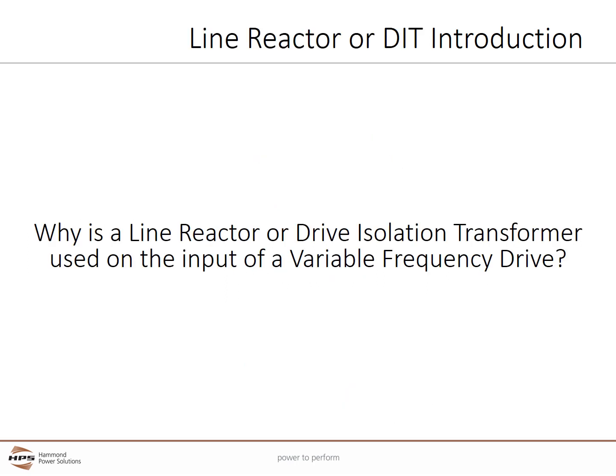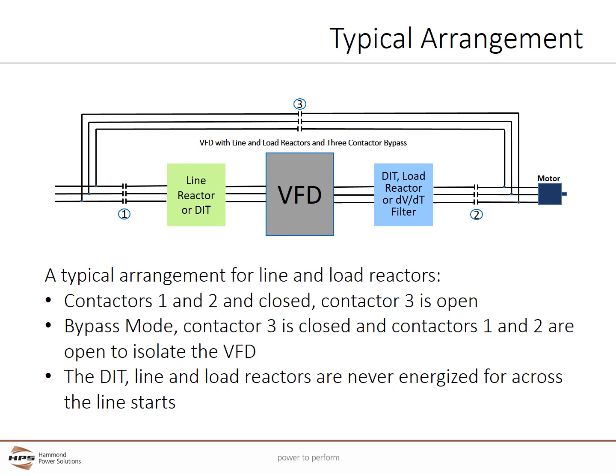Let's begin the discussion on why a line reactor or a DIT is used in an application. As we discuss line reactors and drive isolation transformers, we will refer to this diagram several times. This represents a typical VFD with an arrangement for both line and load DITs and reactors. This is also wired in a classic 3-contactor bypass arrangement.